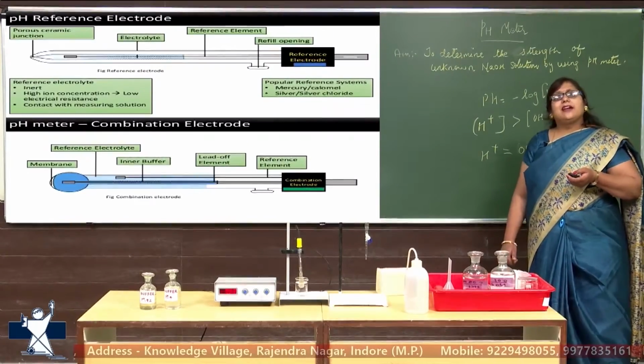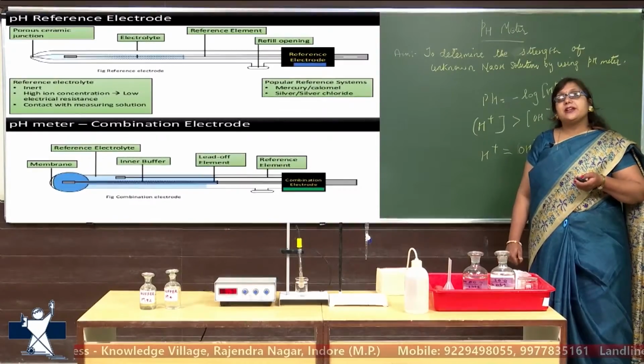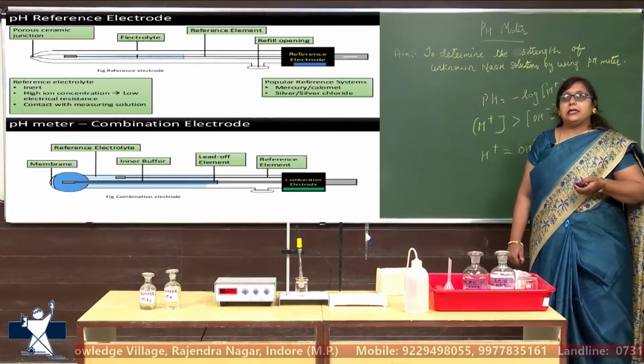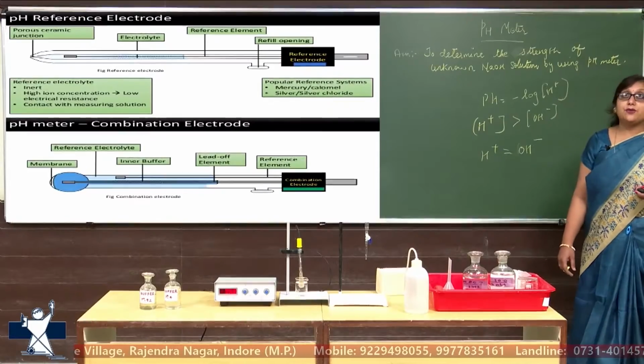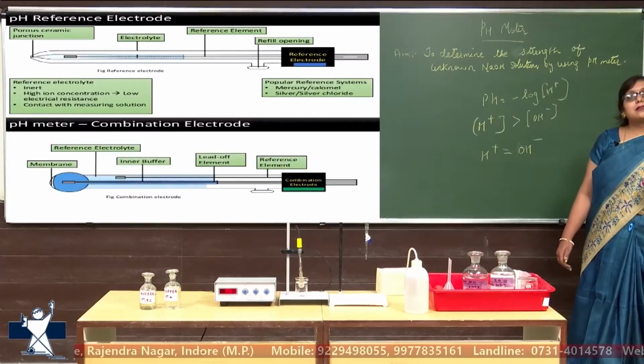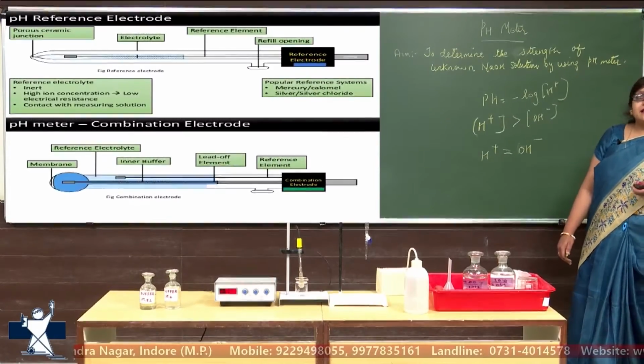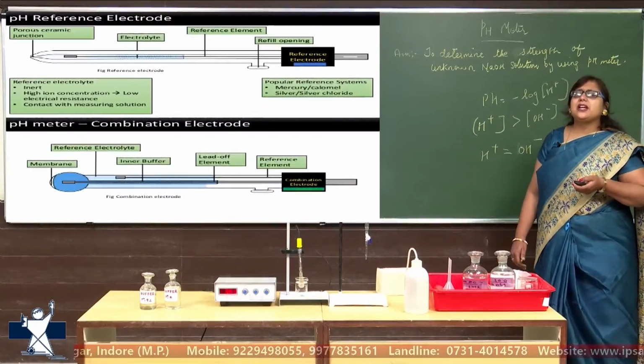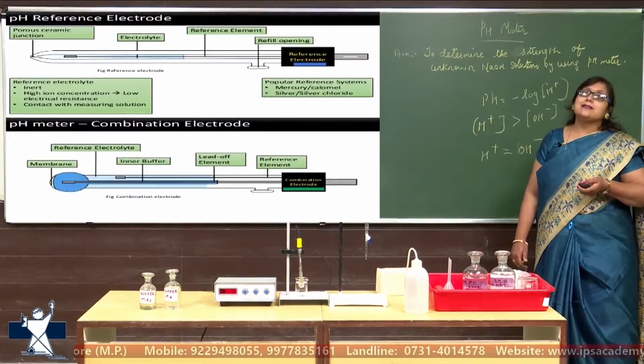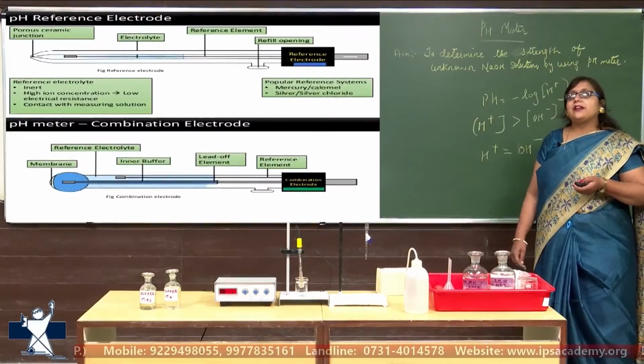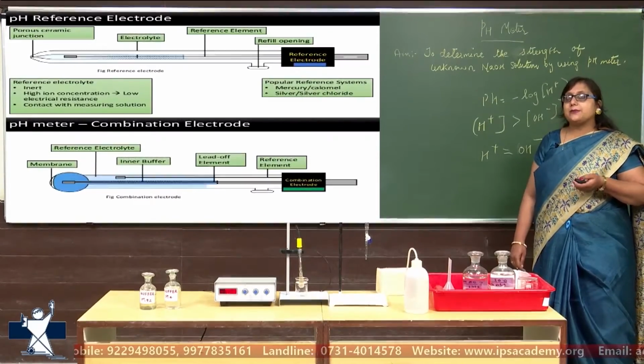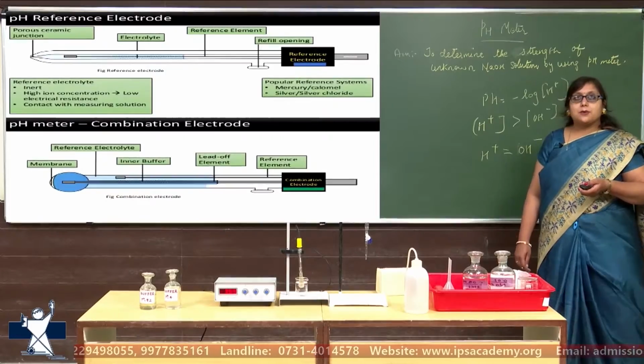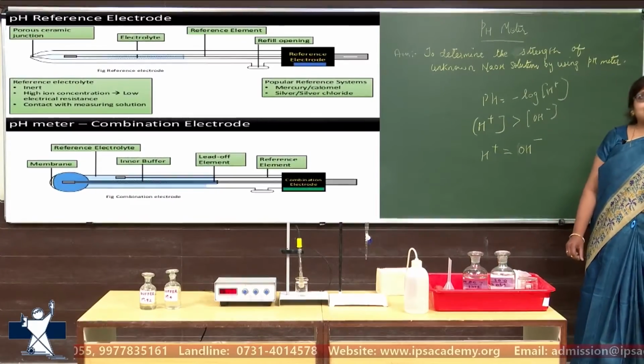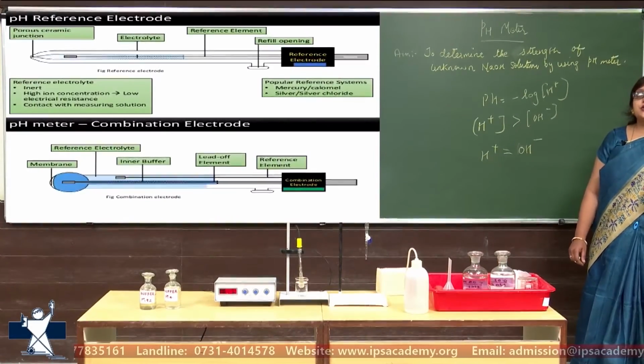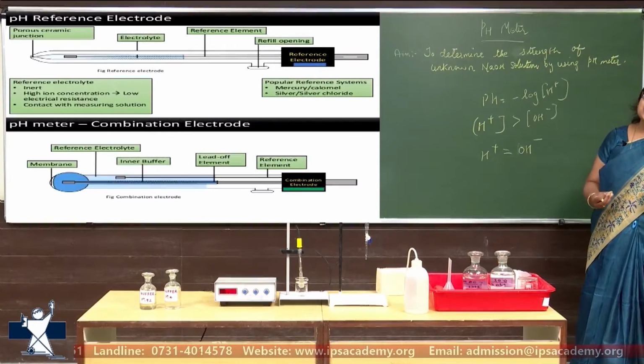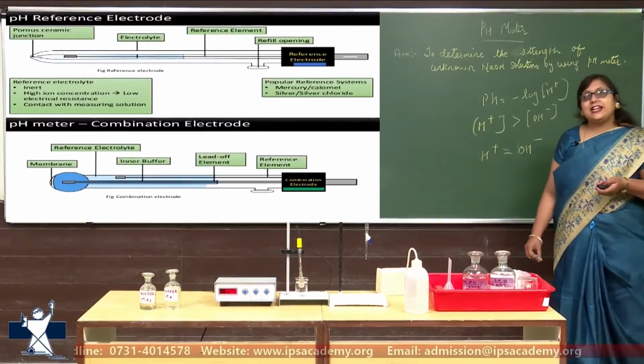A reference electrode is made up of a porous ceramic junction, which is a non-conducting material. Inside it has silver electrodes, or mercurous chloride if we are using that, and the reference element, and it has a refilling opening. Whenever the liquid dries, we can refill it. What is the popular reference system we use? We can use the mercury calomel system or the silver chloride system. And what does a reference electrode do? It is inert in nature, has high ion concentration, and contacts the measuring solution. It is used for the completion of the electric circuit.